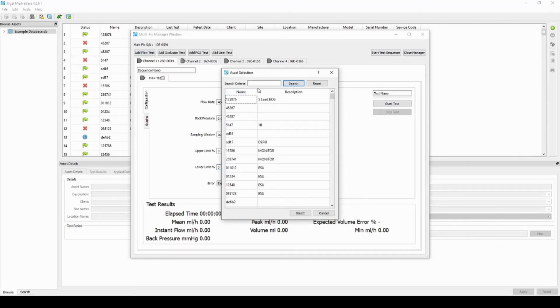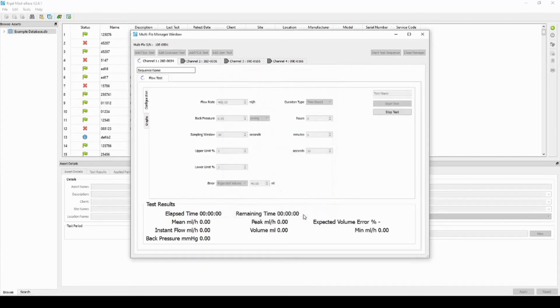We can start the test. So you need to select an infusion. We'll select a run of the asset IDs number, so you need to create an asset ID first before you do this test if you want to save the results to that specific asset ID. And now the test has started, so we need to go back to the infusion device and start the pump.